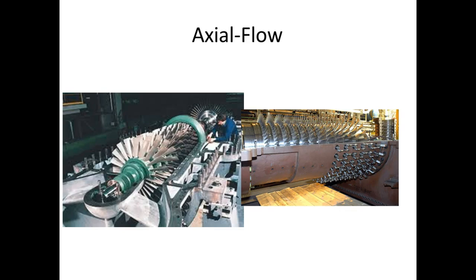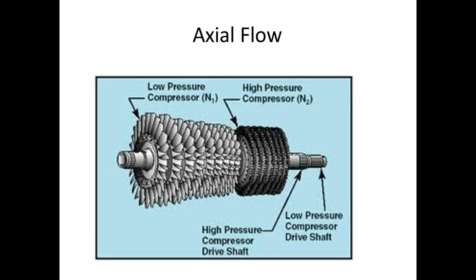Very simple compressors. These are what we call axial flow compressors. And basically they work like jet engines. So what we have is we spin this thing with a prime mover, and it starts in with these big old blades with a lot of space. And as it moves through the compressor, the blades get closer together, which does what? Compresses the air. These guys can create a lot of flow. They can't create a lot of pressure, but they can create a lot of flow. So this would be a better picture of an axial flow compressor.